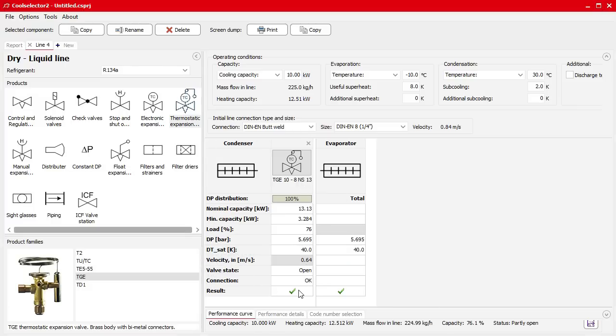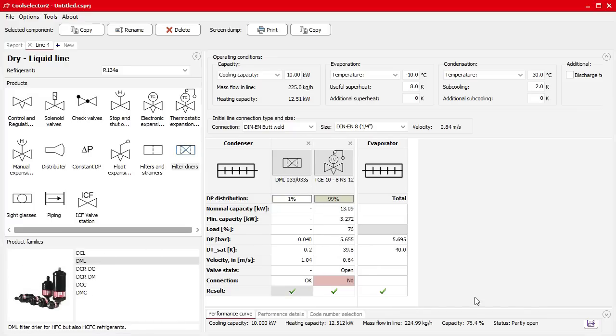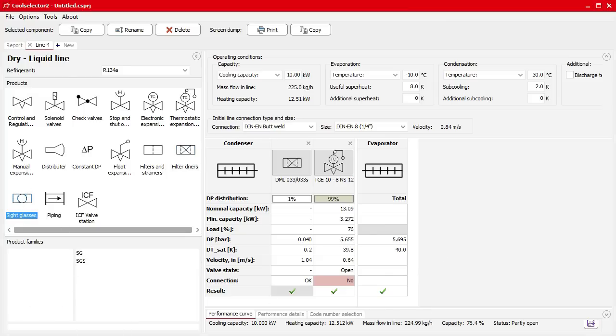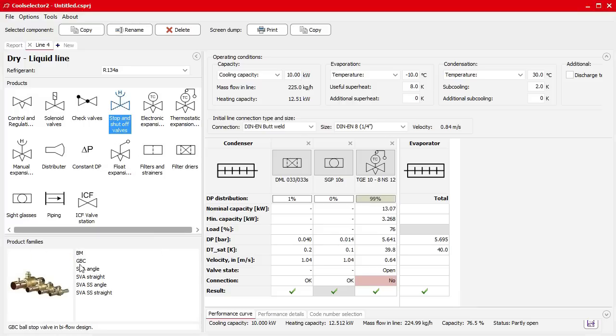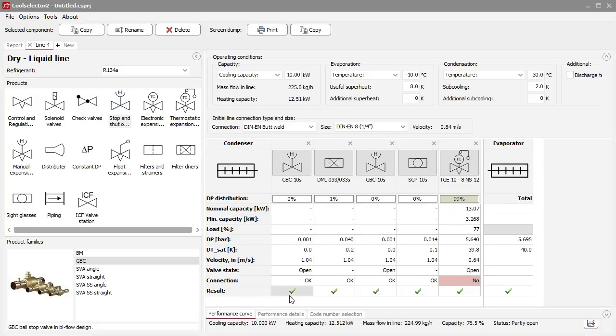Next we want to add a filter dryer — I'll choose the DML product line and drag that in. The connection is okay and the result is applicable to the system, although the connection between the filter dryer and the thermal expansion valve doesn't match, so we'll correct that later. We'll also add a sight glass — I'll go with the SG line, placing it just before the expansion valve, and that's applicable with a good connection. Then we'll add ball valves by selecting stop valves and placing one either side of the filter dryer — the connection is good and applicable to the system.